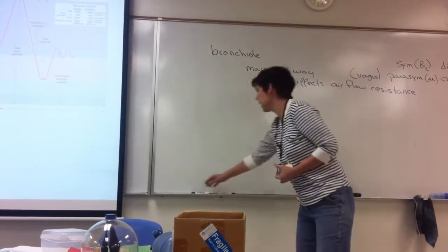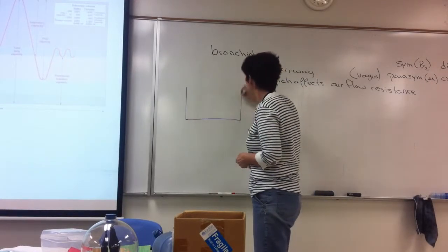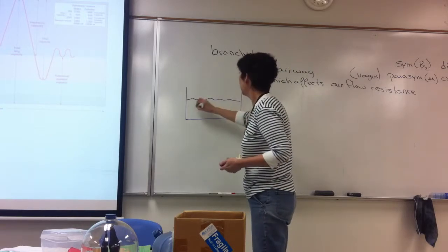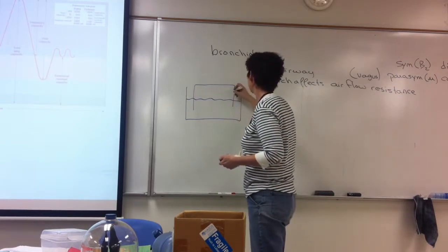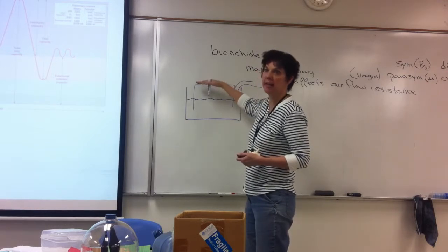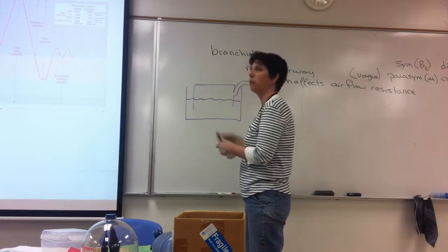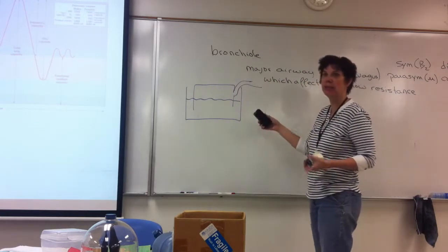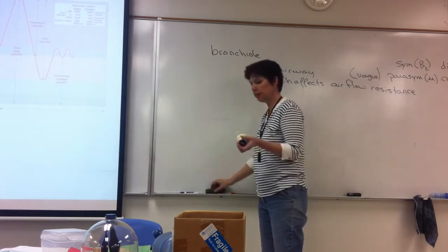A wet was just a box of water with another box, so you would have water here, another box placed upside down with a tube, and when you breathe into that tube, it would raise that box, and a little chain would kind of measure which way. But with all that moisture, it was more conducive to bacterial growth inside the tubing and everything, and so we switched to just using the dry spirometers.